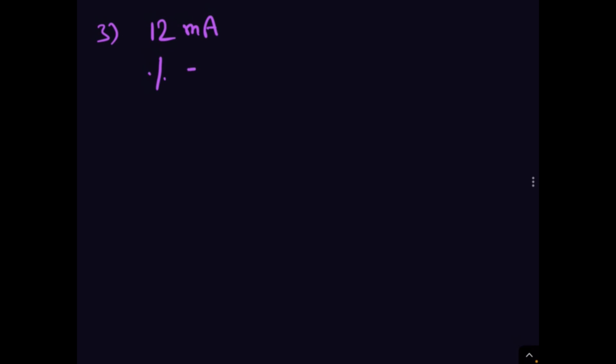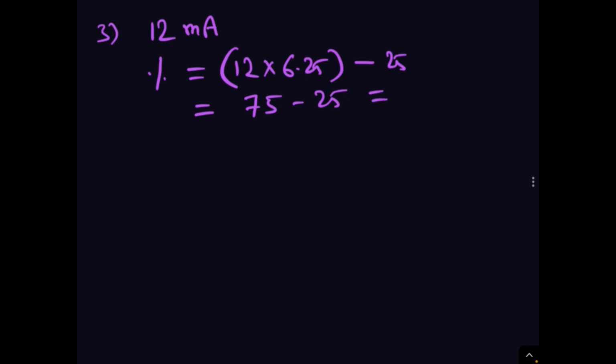Third one, 12 milliamp. Percentage is equal to 12 into 6.25 minus 25, which is 12 into 6.25, which is 75, minus 25, that is equal to how much? 50%. So 12 milliamp is equivalent to 50%.